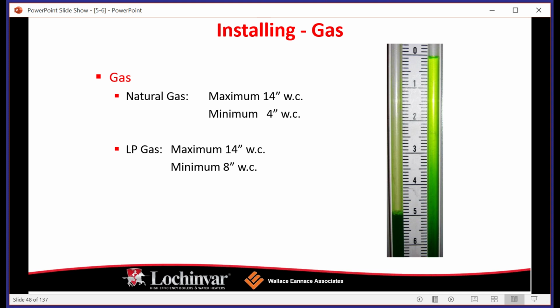Now, gas pressure. If you see on the right-hand side of the slide, there's a crazy looking device, which I hope everybody knows what that is. That is a manometer. What a manometer does is it measures the gas pressure coming to the appliance in something called inches of water column. Every single one of you as a contractor, or contractors that you work with as sales or representative personnel, should have a manometer. The one we're seeing on the right-hand side is called a slack tube or U-tube manometer. More often than not nowadays, we see digital manometers, simply for ease of transport mostly.